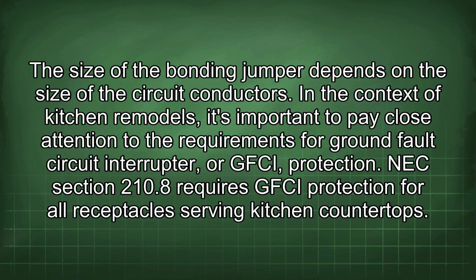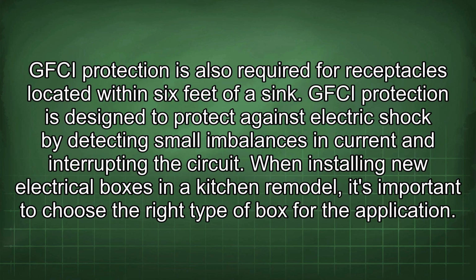In the context of kitchen remodels, it's important to pay close attention to the requirements for ground fault circuit interrupter, or GFCI, protection. NEC section 210.8 requires GFCI protection for all receptacles serving kitchen countertops. GFCI protection is also required for receptacles located within 6 feet of a sink. GFCI protection is designed to protect against electric shock by detecting small imbalances in current and interrupting the circuit.